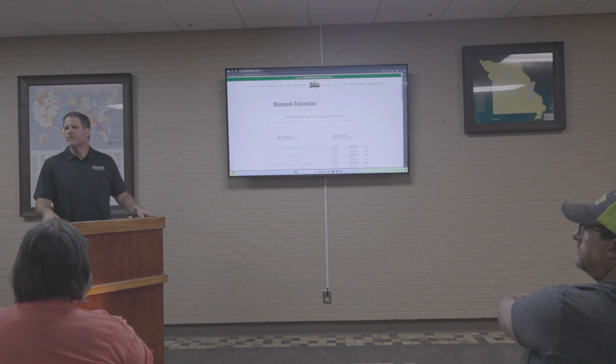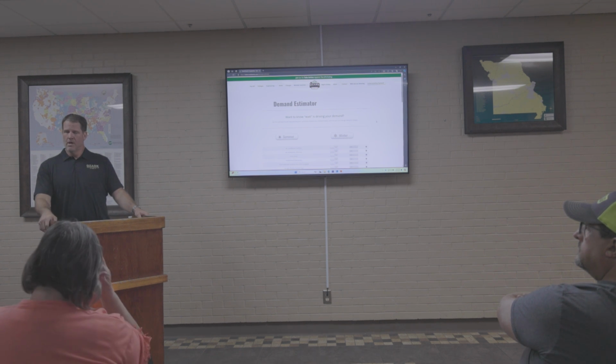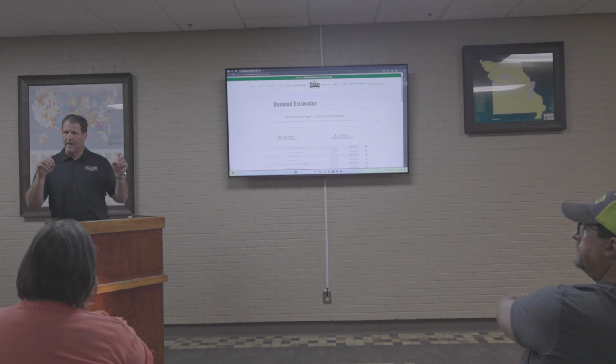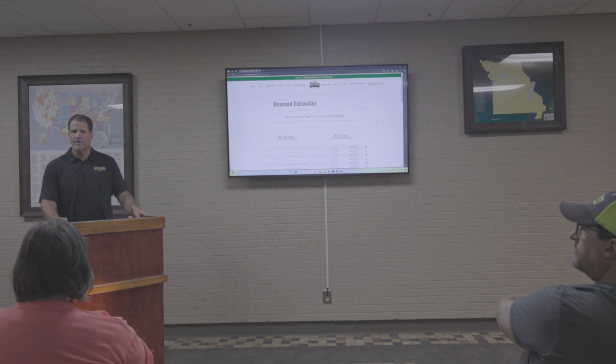Aren't you just moving the peak demand time from one hour to a different hour? That's some of the issue with time of use, because you have what we would call a shoulder peak. So maybe it is from 4 o'clock in the afternoon to 8 o'clock in the evening, and now you have a peak at 9 o'clock that you've never experienced across the system. That is a concern with time of use, that you set a shoulder peak later on that you didn't anticipate. So there are lots of things to look at and consider when you talk about rates.